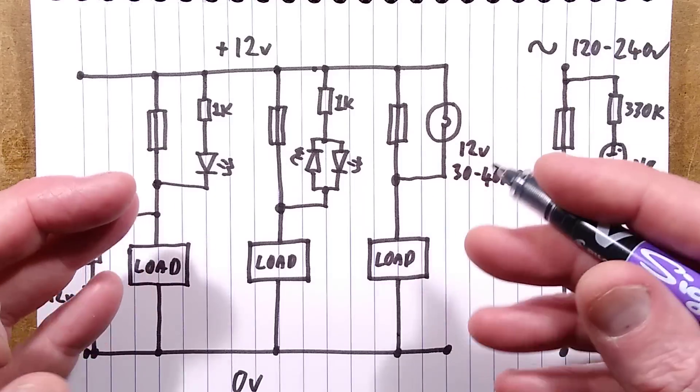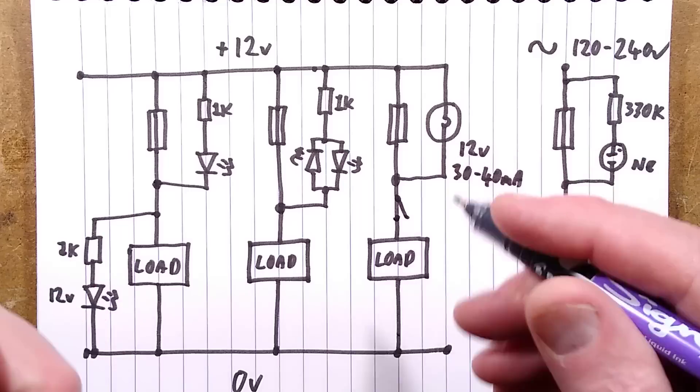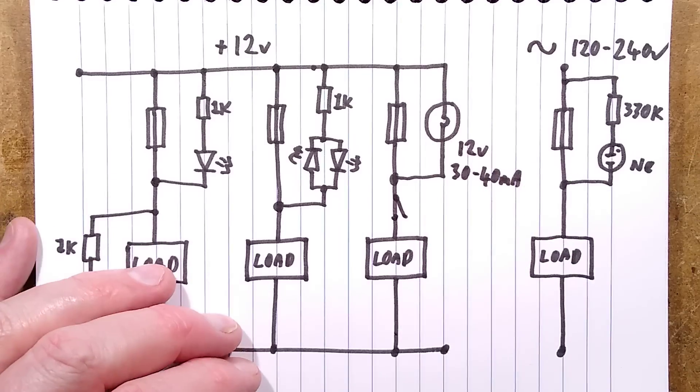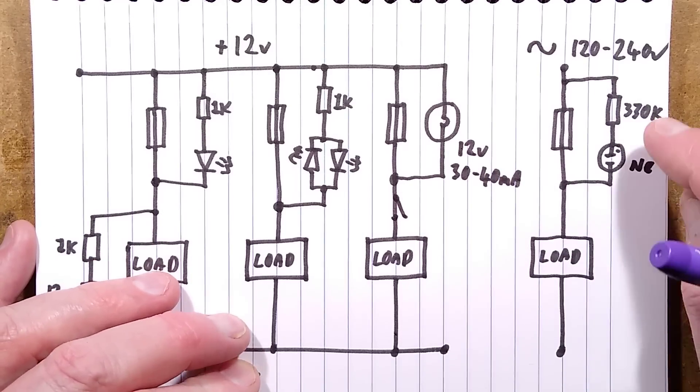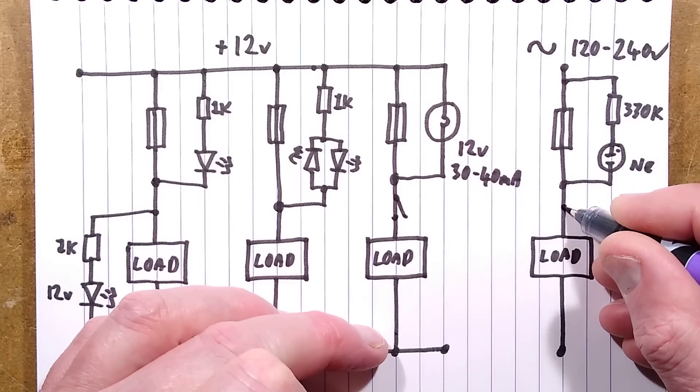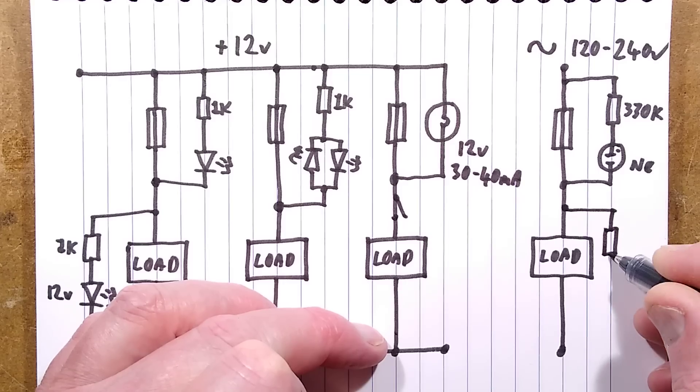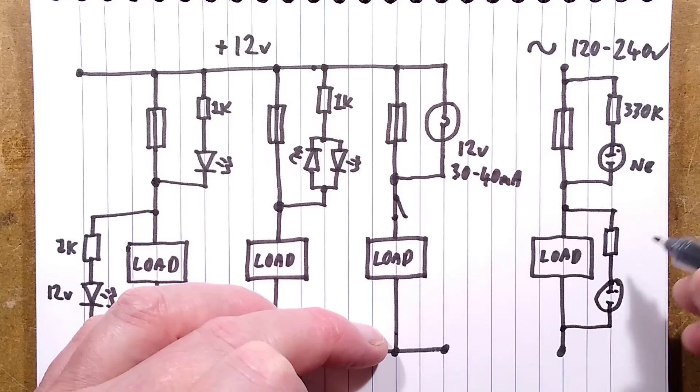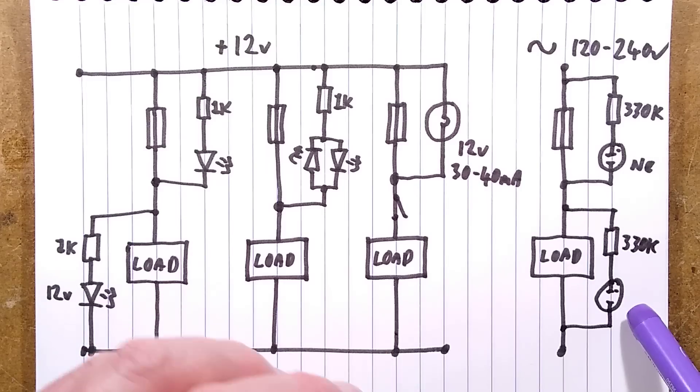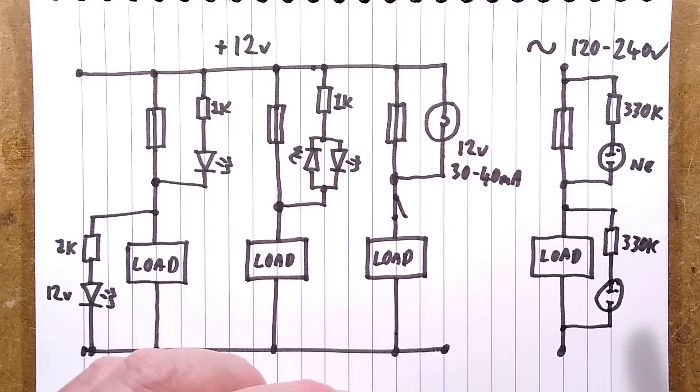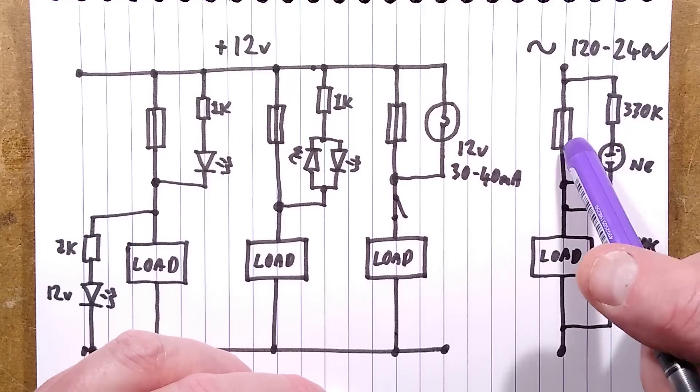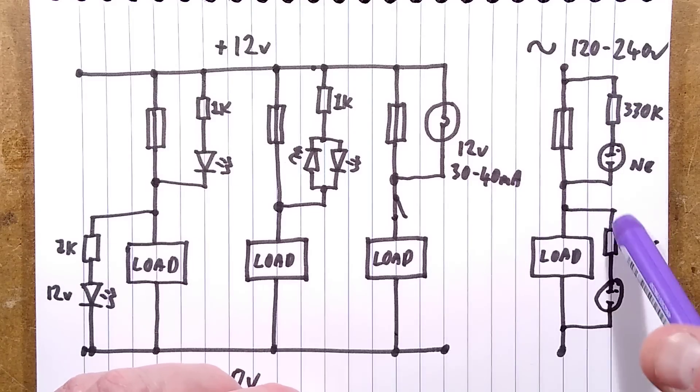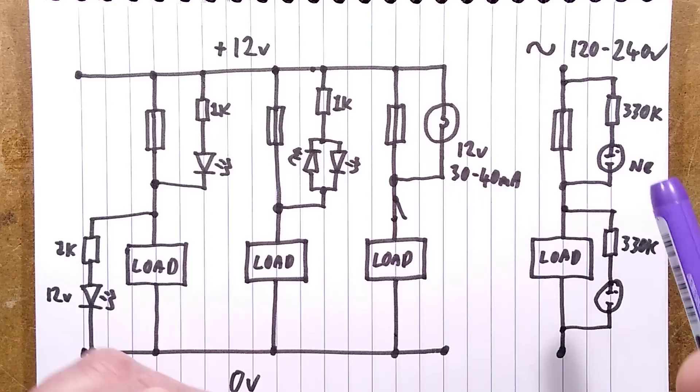That's assuming there aren't things actually activating, you know, that you might have a relay contact in here that disconnects the load, and it's only when it's connected that it blows the fuse. So you'd actually have to test it under active conditions. The other option, and I've used this myself, is I often on my designs, I'm a big fan of putting neons, neon indicators on main circuitry to show when a circuit board is powered. So the technician working on it can see, just got a reminder that it's active. So in this case, the neon down here would light up to show that the circuit was active, but in the case of the fuse blowing again, current would flow through the resistor and the neon instead, and the neon indicator would light via the load, or even if the load was broken, it would actually light via the other one, and you'd get both on. But if this indicator here is lit, then there's a fuse blowing.